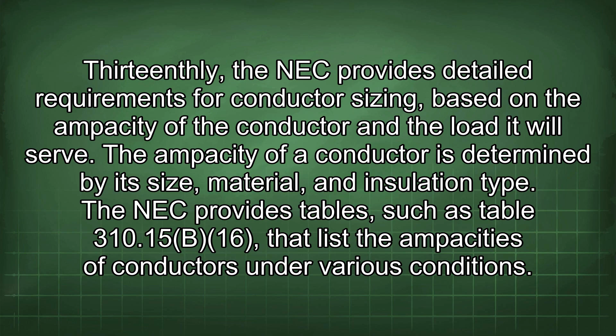Thirteenth, the NEC provides detailed requirements for conductor sizing based on the ampacity of the conductor and the load it will serve. Ampacity is determined by the conductor's size, material, and insulation type. The NEC provides tables, such as Table 310.15(B)(16), that list conductor ampacities under various conditions.